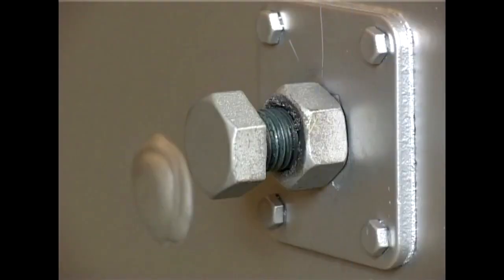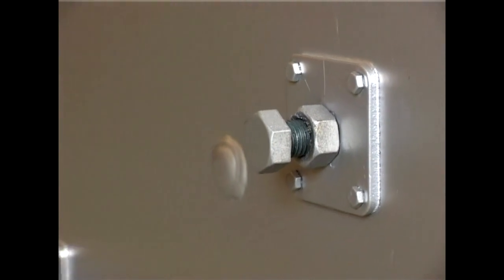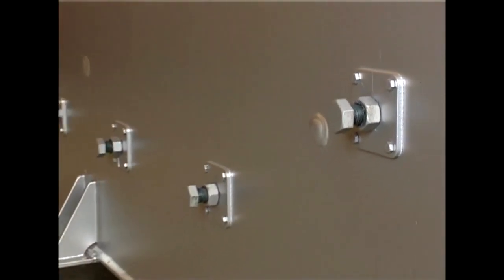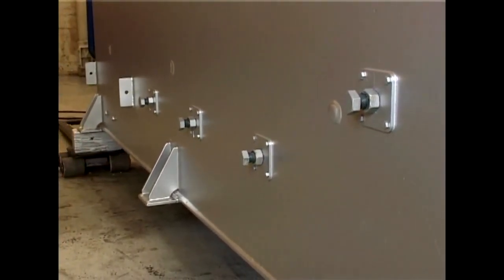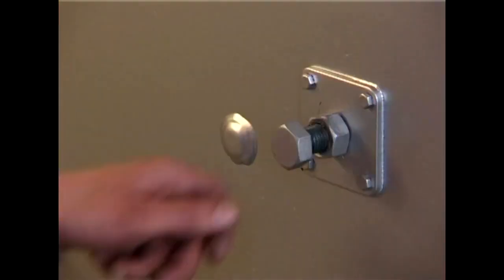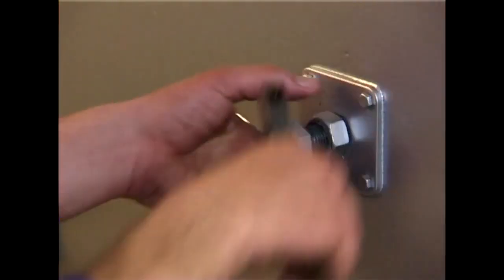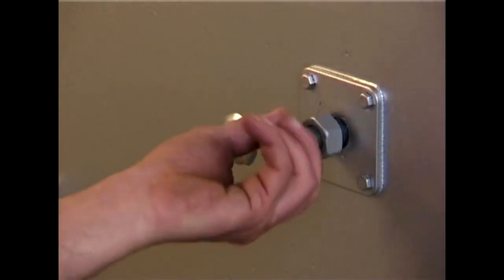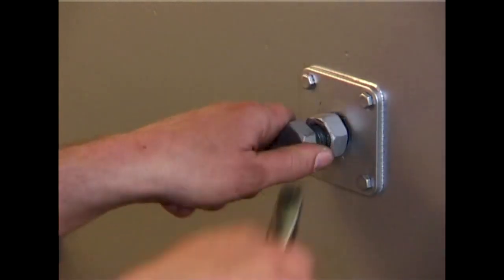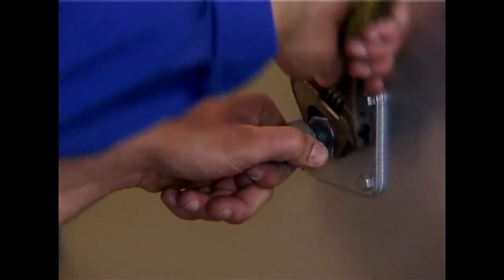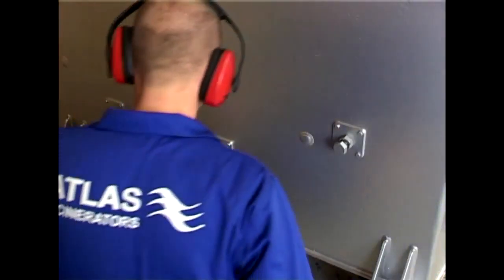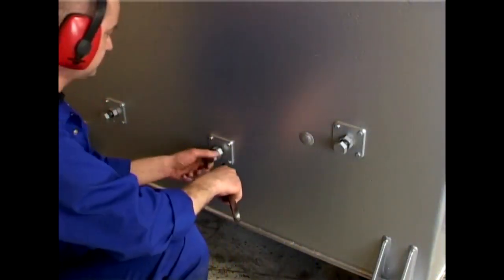The next step is adjusting the air nozzles. The air nozzles lead air from the cooling air jacket into the combustion chambers. Adjust all the air nozzles by turning them clockwise until they are completely closed. This will give the shortest heating up period of the incinerator and reduce the consumption of diesel oil.